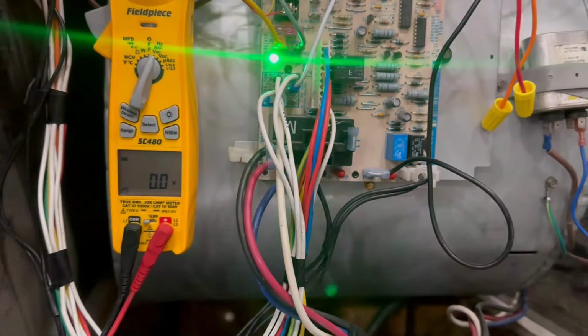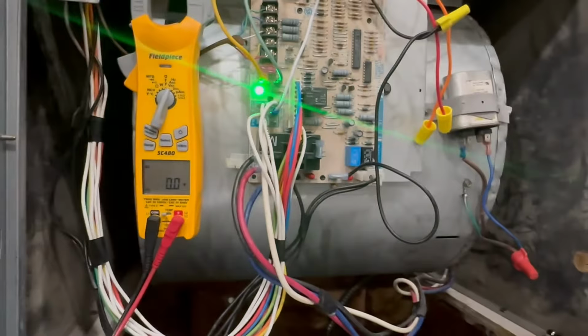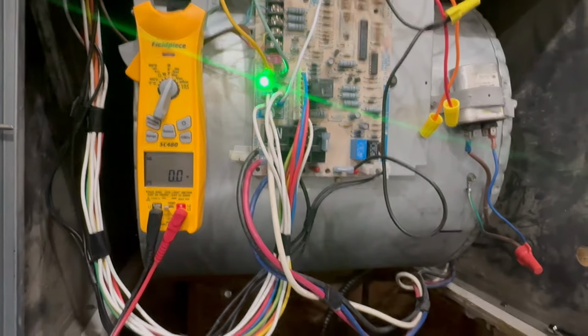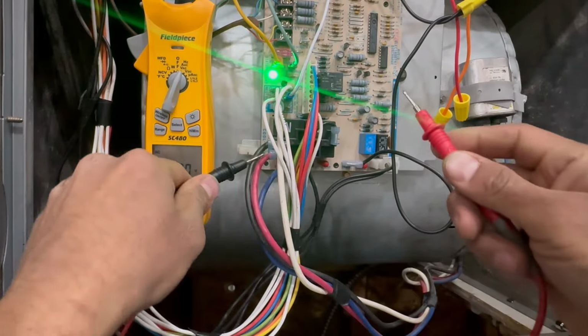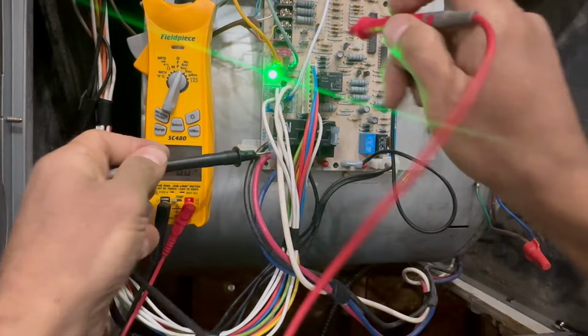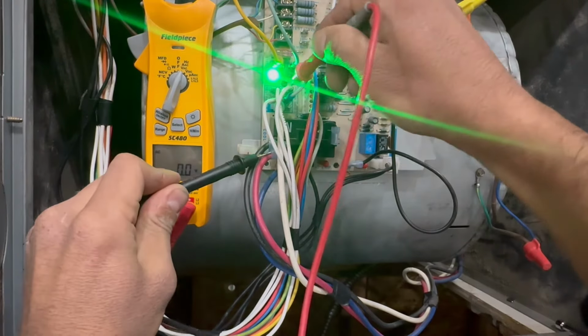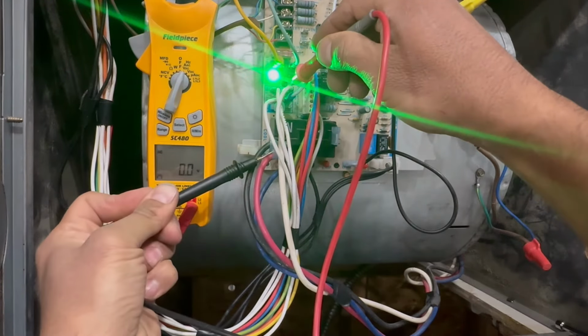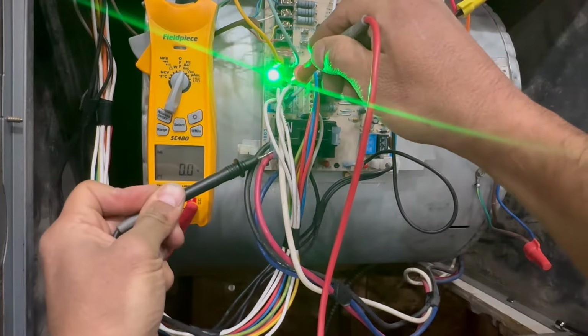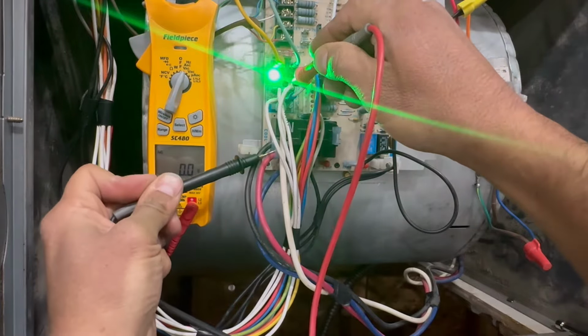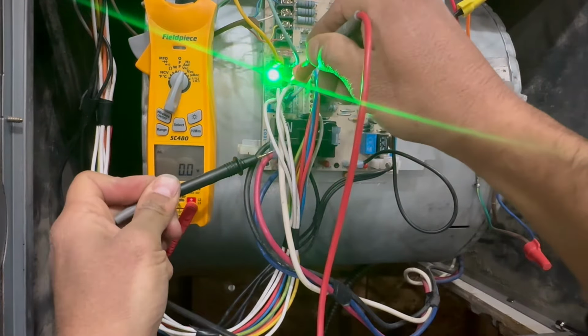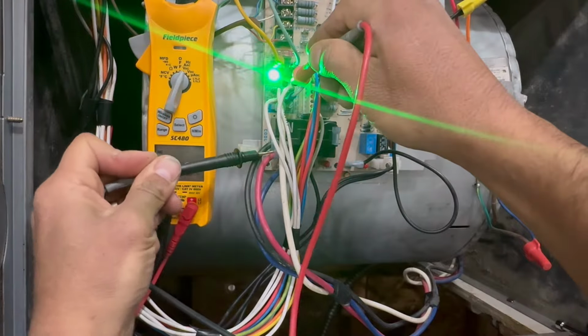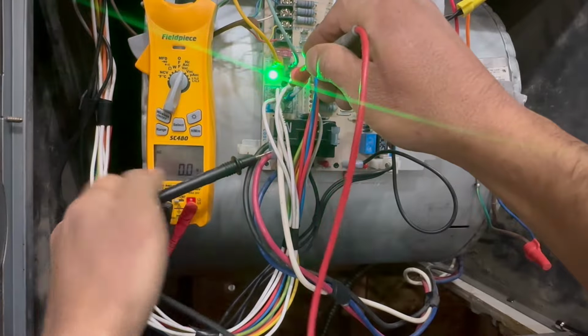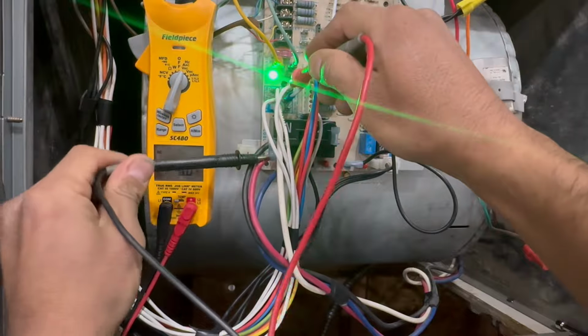So it's using the red wire, which is a lower speed than the black one, to send 120 volts. But I'm going to confirm, look, it's not sending 120 volts. I'm going to check that one in neutral. You see, you look at my meter. It's not sending 120 volts yet. It's still not on. We're going to wait a couple seconds. And you're going to see now that the blower motor is going to turn on right now. So let's give it a second.